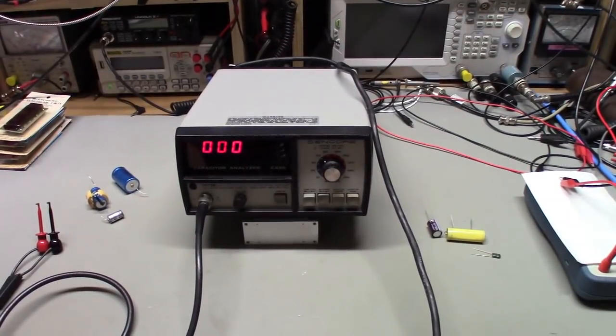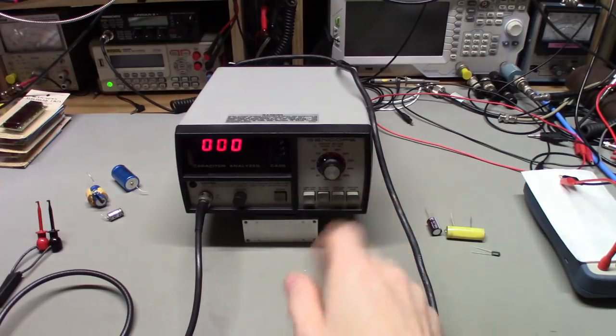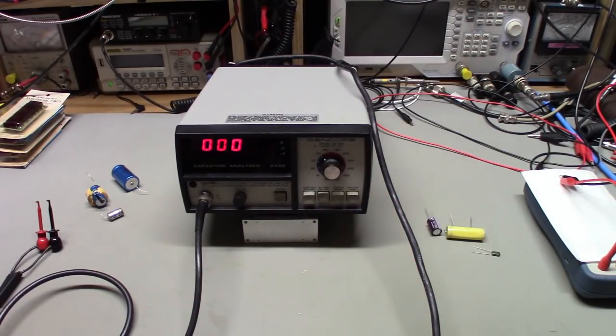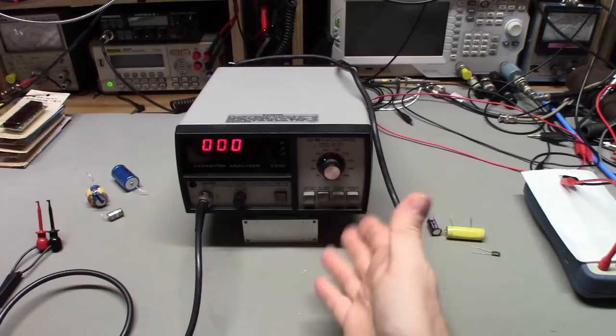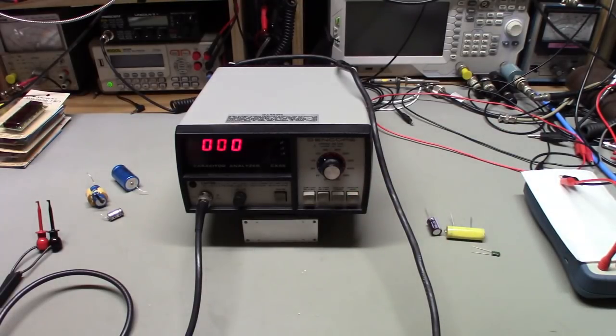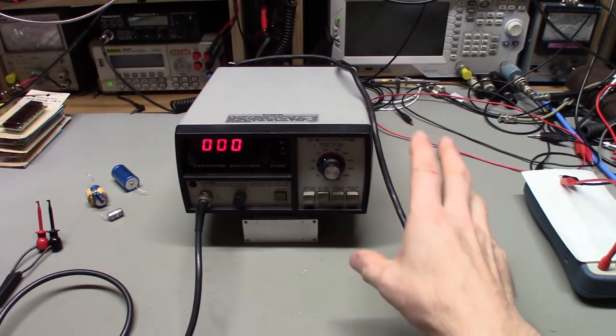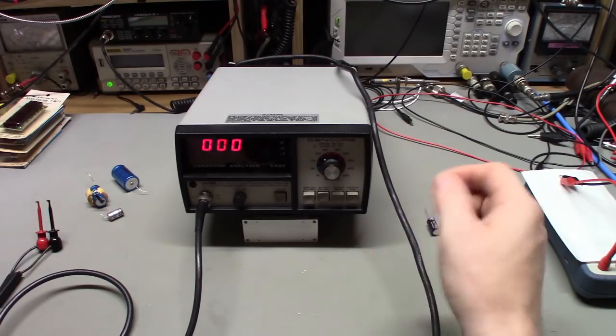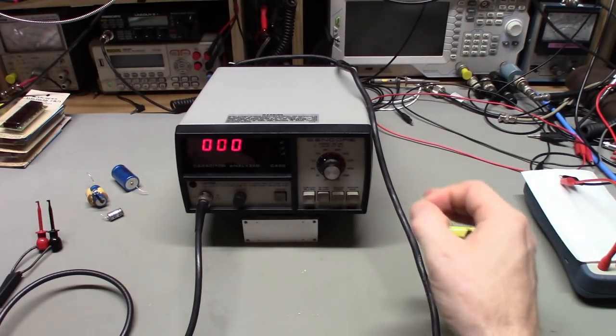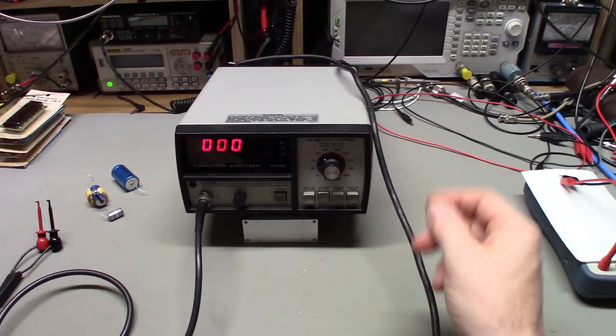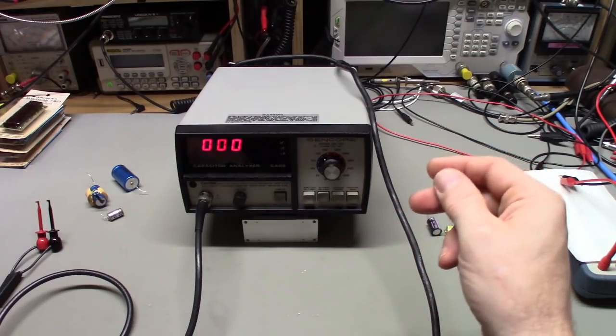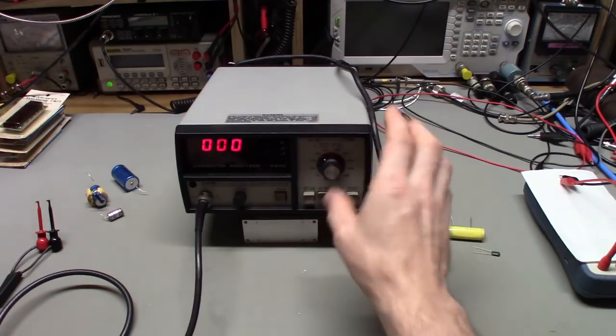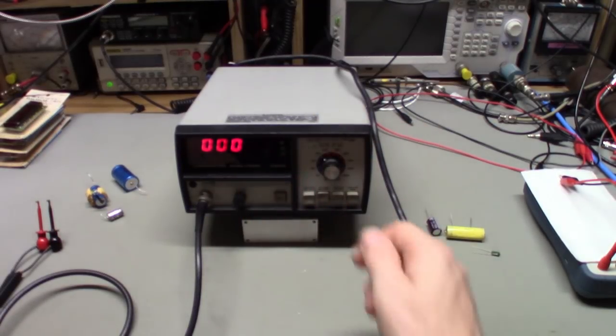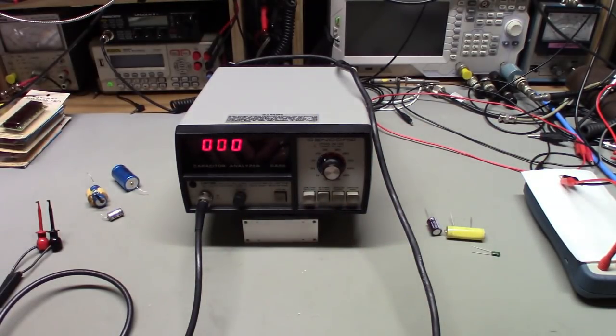Okay, so I changed out the 4 electrolytic capacitors in it. Did run through the calibration procedure, which, like I say, it's only a couple adjustments, because it only does one thing, test capacitors. I did go ahead and test the ranges, because like I say, I do have a capacitor standard here, and tested it. I did make slight adjustments to it, but yeah, the capacitance actual measurements were within the tolerance. So if you were to go by the meter's accuracy as the manufacturer's advertised tolerance, it was still within its tolerance. But I did make some very fine-tuning adjustments to that.